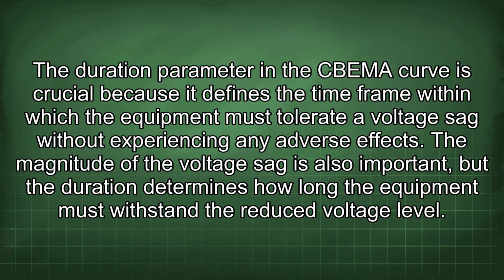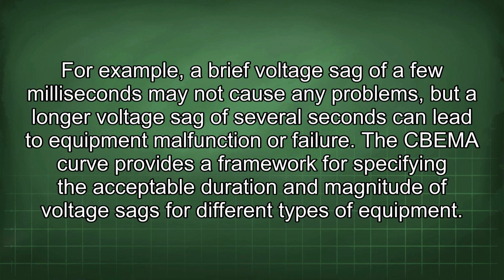The duration parameter in the CBEMA curve is crucial because it defines the time frame within which the equipment must tolerate a voltage sag without experiencing any adverse effects. The magnitude of the voltage sag is also important, but the duration determines how long the equipment must withstand the reduced voltage level. For example, a brief voltage sag of a few milliseconds may not cause any problems, but a longer voltage sag of several seconds can lead to equipment malfunction or failure.